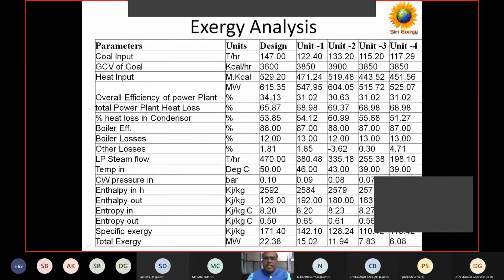So that means overall efficiency at the design stage is 34%, whereas actually we are getting only 30-31% efficiency in practice. So what are the losses? Almost 65, almost 70%. We are losing 70%, so we analyze further where we are losing. One is in the condenser; in the condenser itself we are losing almost 55 to 60%. Then boiler efficiency is somewhere around 85%, 88%, which means in the boiler we are losing 12%. So we are losing 53 and 60 here, out of 65, in these two major equipment. In these two major equipment we can improve performance wherever possible.